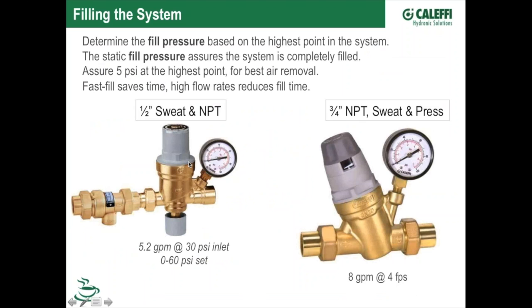This is a high flow valve. There's no need to bypass this valve and have a workaround. When you start this valve up, the first time flowing through it, as long as you have 30 pounds inlet pressure coming in from your city or your well pressure here in your building, you're going to get about a 5.2 gallon per minute flow going through this device. And that's typically enough to purge most residential systems. Sometimes you have to break them down into pieces if you've got a lot of big piping, but that's what we're offering here, is something that will fill the system quickly.